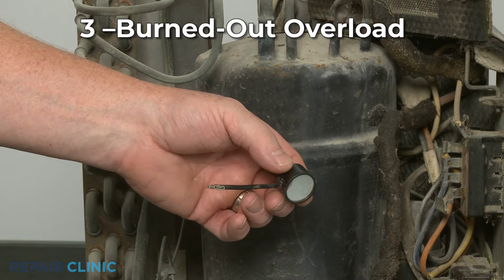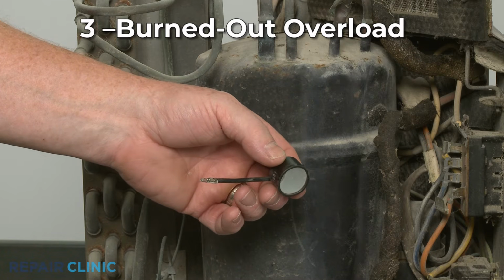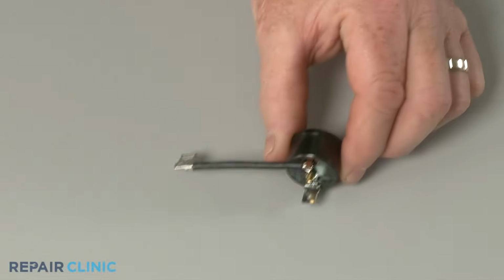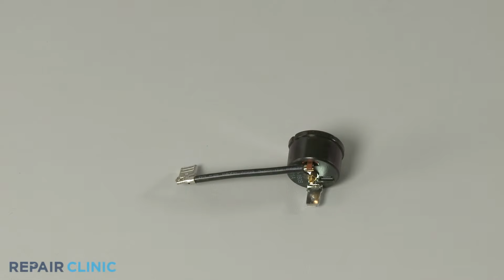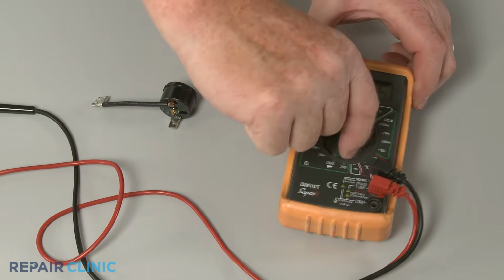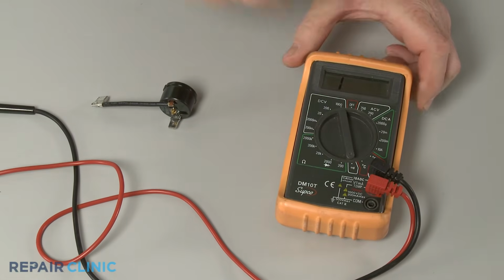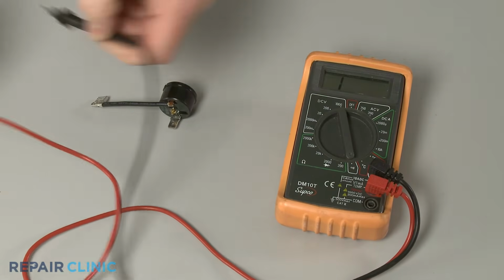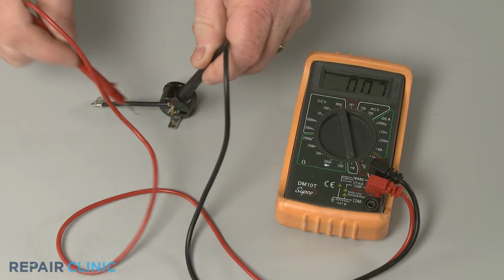An overload protects the compressor from burning out if it draws too much current. Over time, the overload itself can burn out and prevent the compressor from running. If your model has an external overload, you can use a multimeter to test it for continuity to determine if the part has burned out or not.